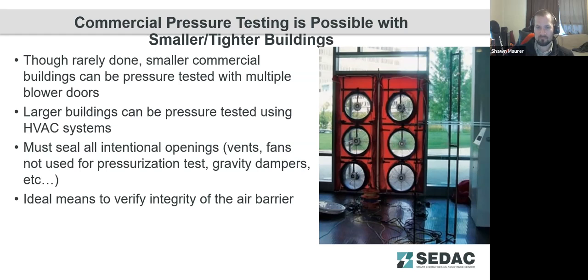A single fan can move about 4,900 CFM at 75 pascals, which is enough to test an envelope, if it's designed well, of about 12,000 square feet, a little bit higher. If you triple those fans up, now you're up to 36,000 square feet. So you can get to significantly sized buildings with this testing, and it's a great way to make sure that the visual checks and design checks you've done on your drawings and detailing are properly installed and you've got good air barriers. We've actually seen this as a great way to catch issues with curtain wall assemblies and storefront assemblies that might be hidden.